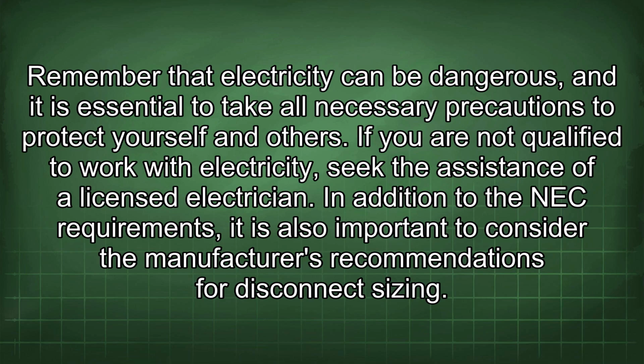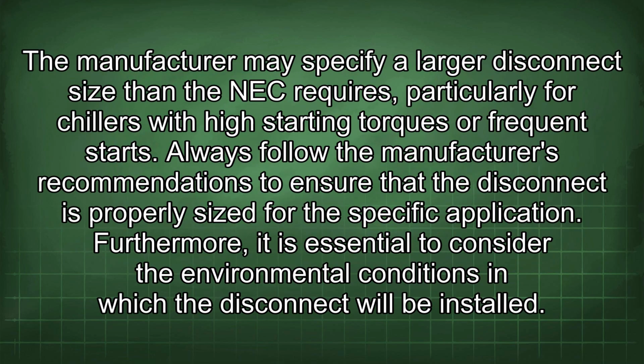In addition to the NEC requirements, it is also important to consider the manufacturer's recommendations for disconnect sizing. The manufacturer may specify a larger disconnect size than the NEC requires, particularly for chillers with high starting torques or frequent starts. Always follow the manufacturer's recommendations to ensure that the disconnect is properly sized for the specific application.